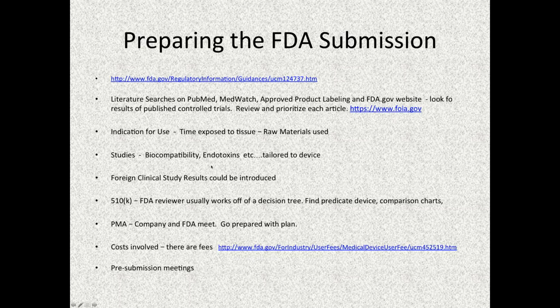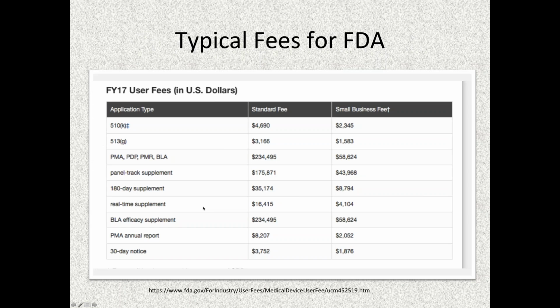Almost every implantable device, and any device that touches the skin and stays on the body for more than 24 hours, requires some form of biocompatibility, and this is an iterative approach. Many times it's best to bring in a chemist and a microbiologist to look at the biocompatibility you want to do on the device and develop a rationale. You can save money by eliminating some of the tests that are required early on, but it's not that you can just say not applicable. You have to give a rationale for why you didn't use it. Foreign clinical study results can be introduced into the FDA under certain conditions.